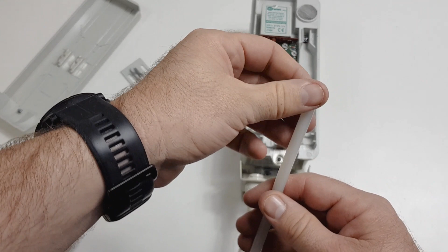It's really, really imperative that your HT cable is always shielded, especially from its partner. You don't want these two touching. We see this all the time, where it comes out of the transformer with cable ties all the way down the job. That's not allowed, and you'll cause yourself a serious cabling issue.